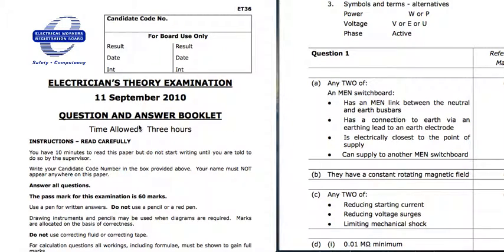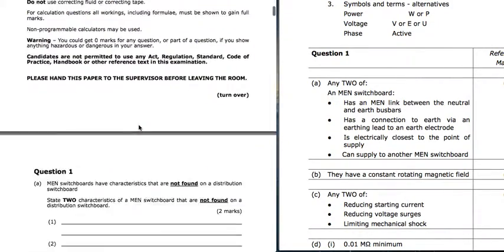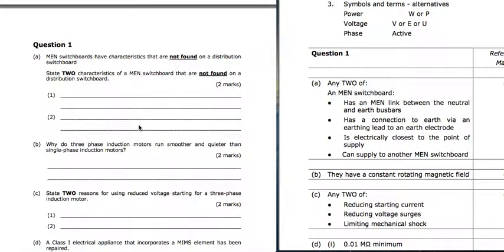This is September 2010. Question 1. MEN switchboards have got characteristics not found on distribution boards. So we want two characteristics. Now an MEN board will have a link between the neutral and earth busbar. You'll have a connection to earth via the earth lead to an earth electrode.